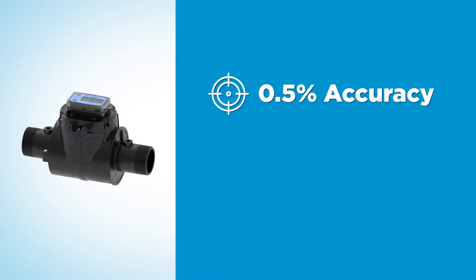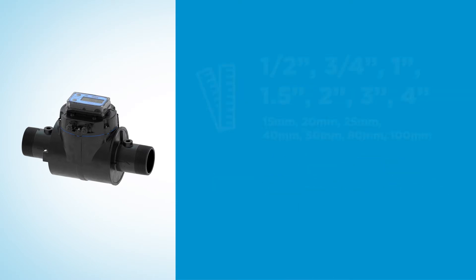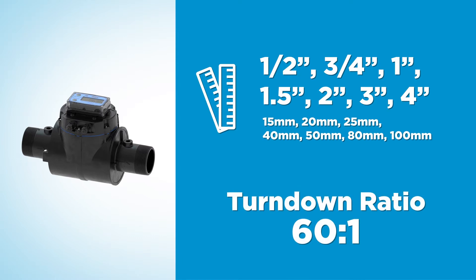The meter is accurate within 0.5% at flow rates from 0.25 to 15 feet per second or 0.08 to 4.6 meters per second. This meter is offered in seven different sizes from 1/2 inch to 4 inch and has a wide turndown ratio of 60 to 1.